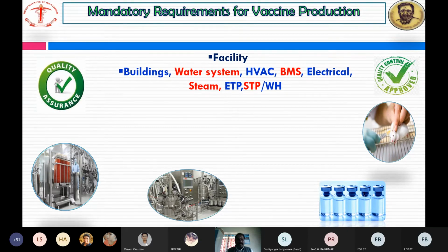Plant steam is generated from normal water, that is pre-treated water. And pure steam is generated from pure water, that is RO, EDI, reverse osmosis and electro-deionization based water. That is the steam for jacket sterilization purpose, either in autoclave or decontamination autoclave or any kind of things used with this steam.